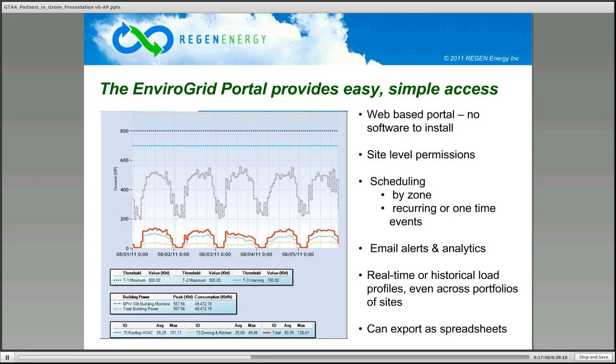An example of scheduling is that overnight the consumption drops to zero, because we're scheduling those units to be off. That's actually been a big part of the saving for them, making sure those units are off when they're supposed to be off. They found during the commissioning stage that a lot of stuff was running overnight and when the club was not open, wasting a lot of money.